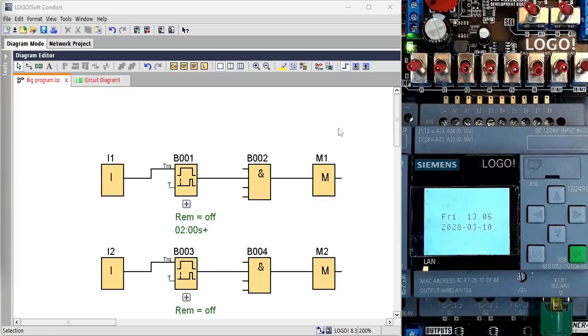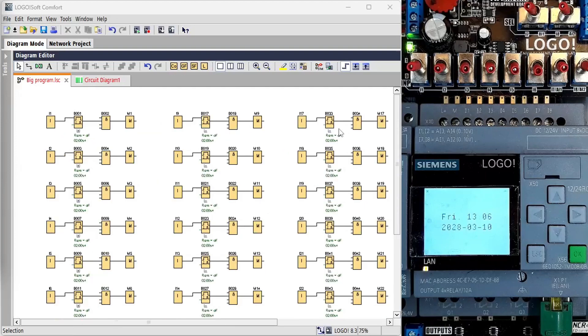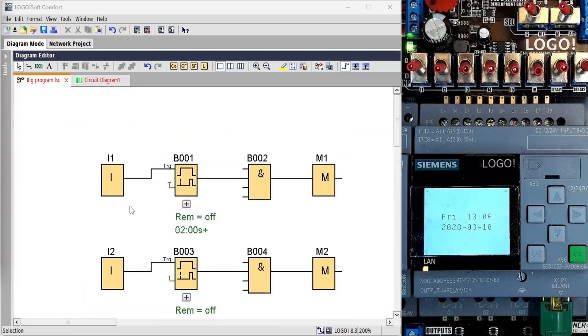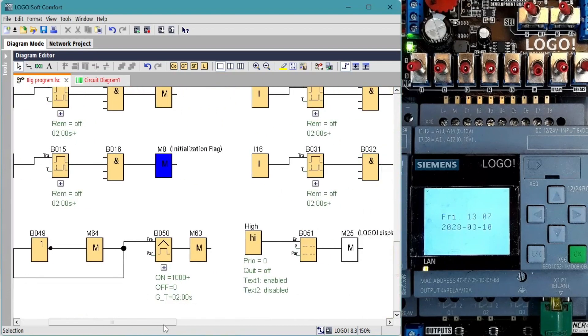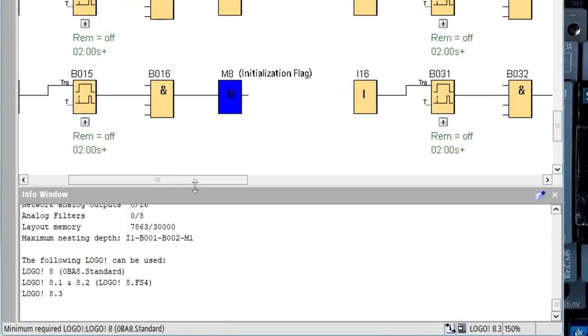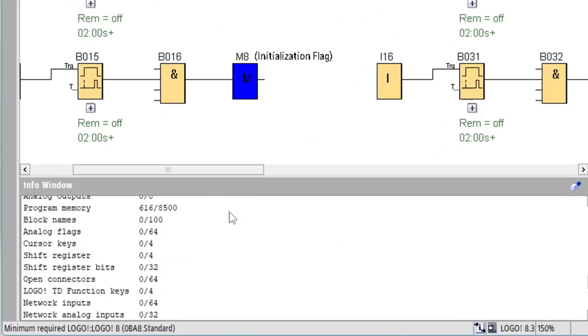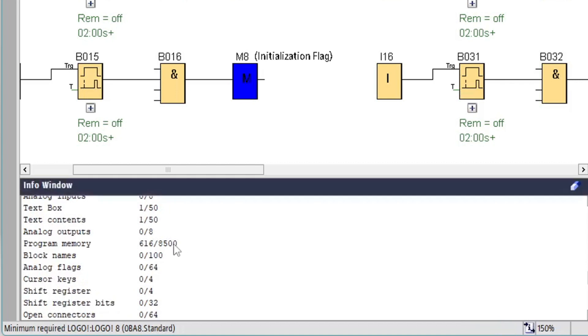This program consists of inputs, timers, ANDs and flags repeated many times. In the bottom we have the same scan time calculation logic. Press F2 and we can see that the program is using 616 out of 8500 available program memory, which is about 15 times our earlier program.